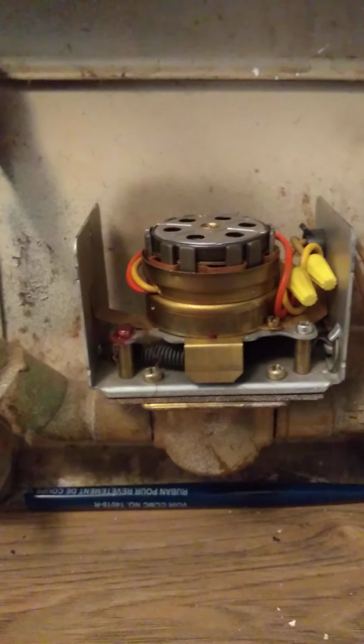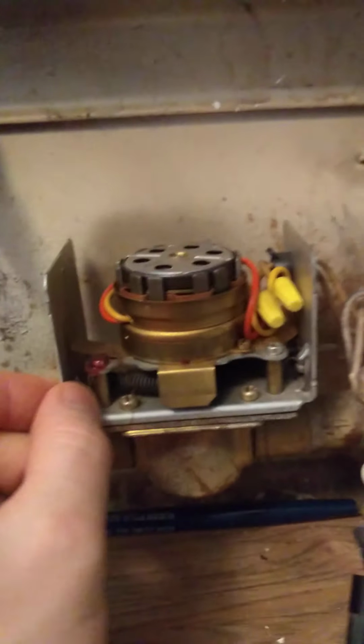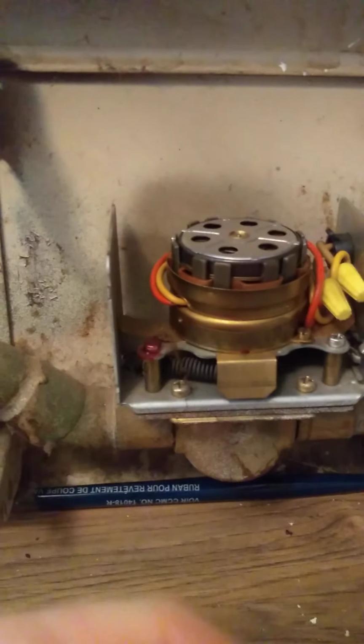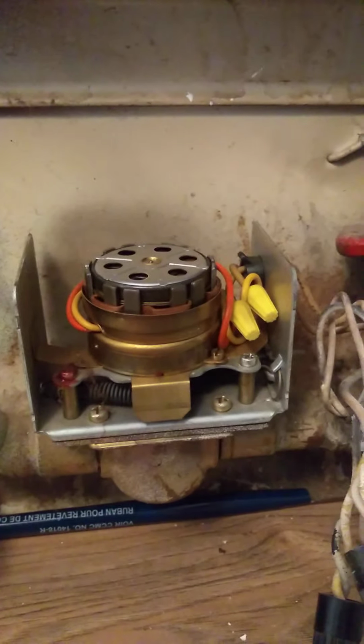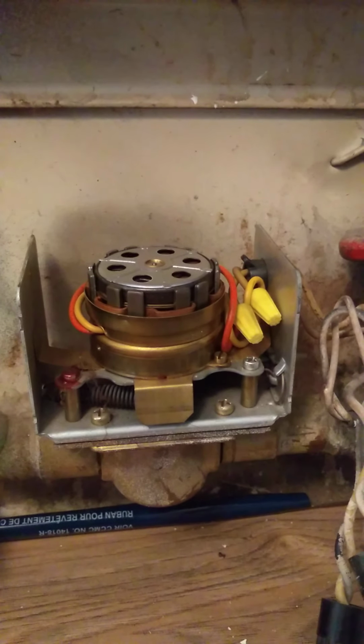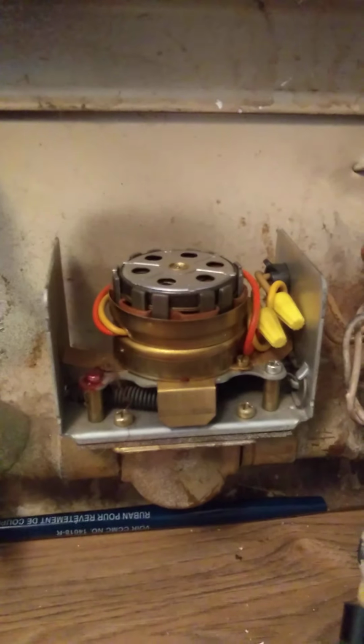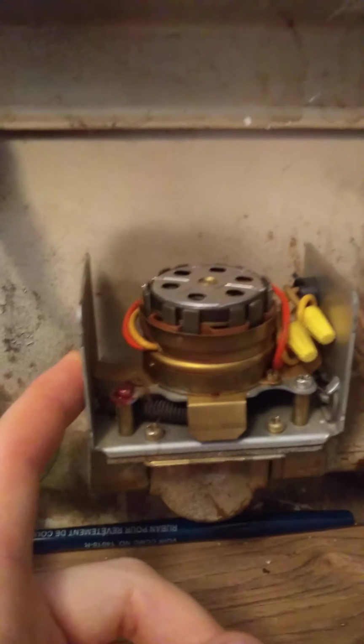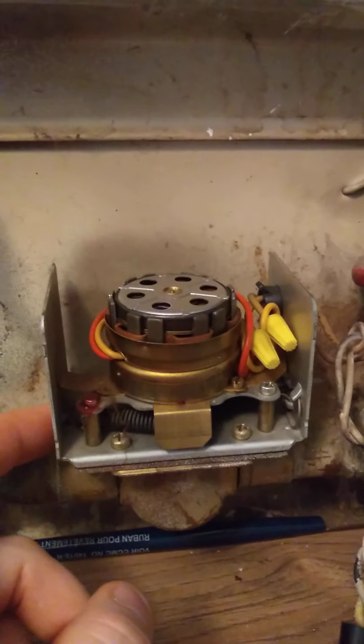They just seem to think that this whole thing is a zone valve. When this is a zone valve, this is a motor that opens and closes it, totally optional. And this unit actually, see this whole little boxed-in unit, I took the cover off it here. This whole unit, it's 4 screws and they just pop off and you can pop another one on. It's a very quick, simple replacement, and there's several videos on YouTube illustrating exactly how to do that. I'm not going to pop mine off because I just don't want to mess with it because I don't have to. It's 4 screws. I mean, I could definitely do it. But if you pop this device off, you just pop a new one on.